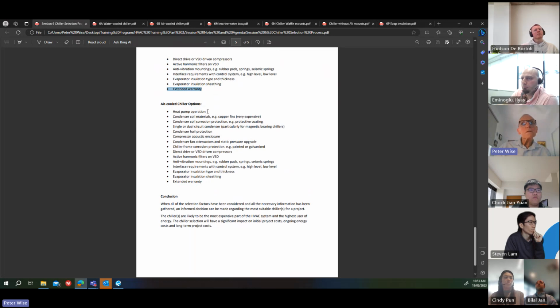For the air-cooled chillers, again, you can have heat pump operation, the condenser coil materials, copper fins, very expensive, but it's available if you want that, or protective coating. Protective coating is a much less expensive option, and there are some very good coatings which will last for, or extend the chiller life for several years. They won't last forever, but you might get another 5 years out of it. And there can be a maintenance program where you might have a look at that protective coating after 5 years and perhaps reapply it. They do have a minor effect on the heat rejection efficiency. Again, you can have single or dual circuit condensers, particularly for mag bearing chillers.